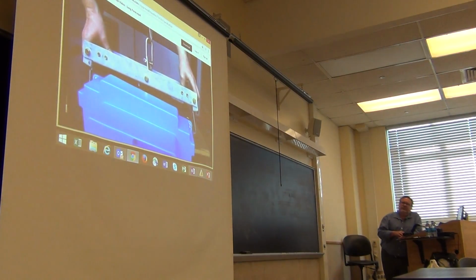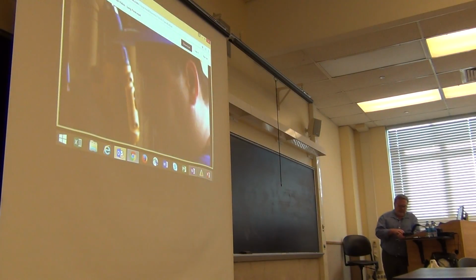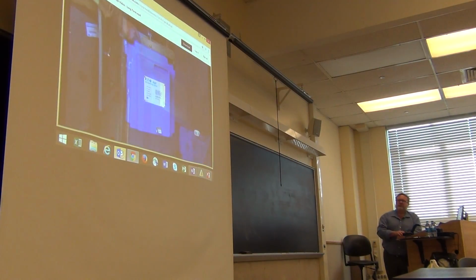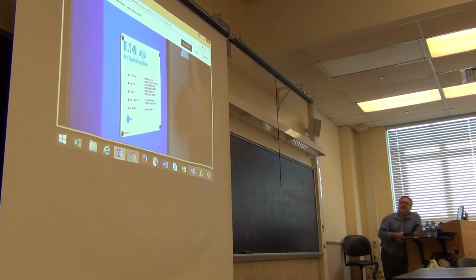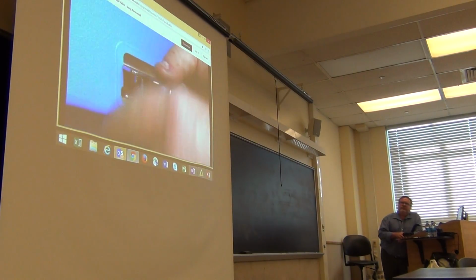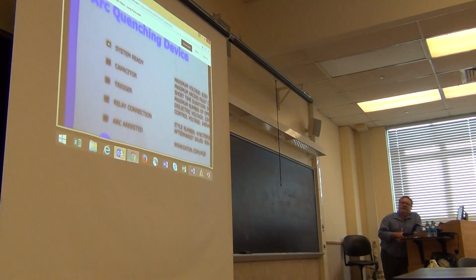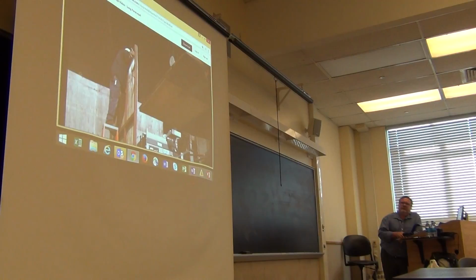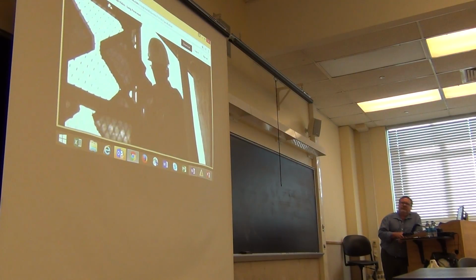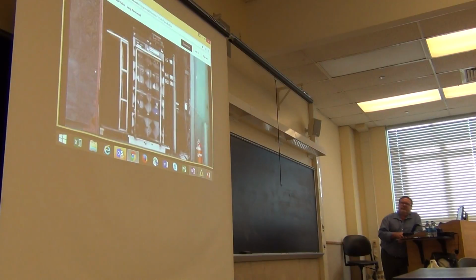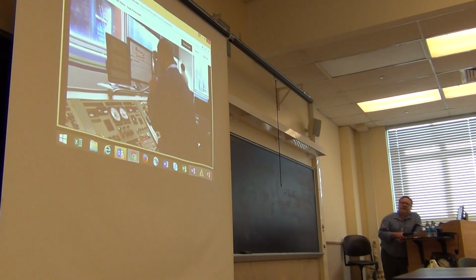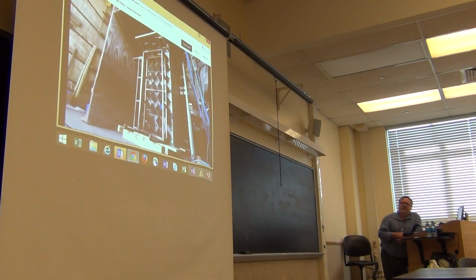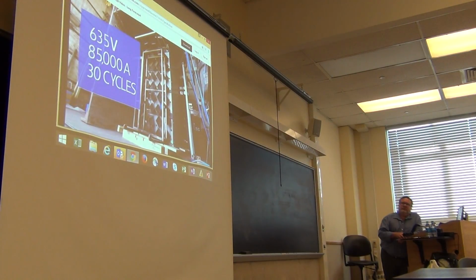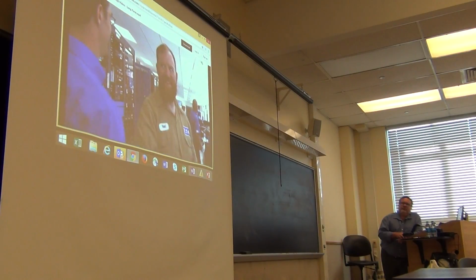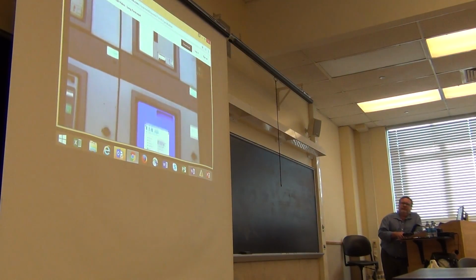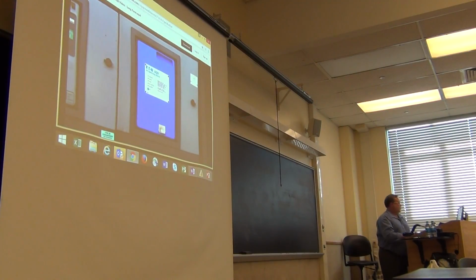Eaton's arc quenching switchgear was developed with that goal in mind. The technology is designed to detect and quench an arc flash event in less than 4 milliseconds. That's less than 1/4 of a cycle, well before the pressure wave reaches peak destruction. The team performed a 30-cycle arcing fault test at 635 volts and 85,000 amps of available fault current. 3, 2, 1. The arc quenching switchgear survived undamaged and had a person been standing in front of the gear, they would not have sustained burns or been injured by flying debris.